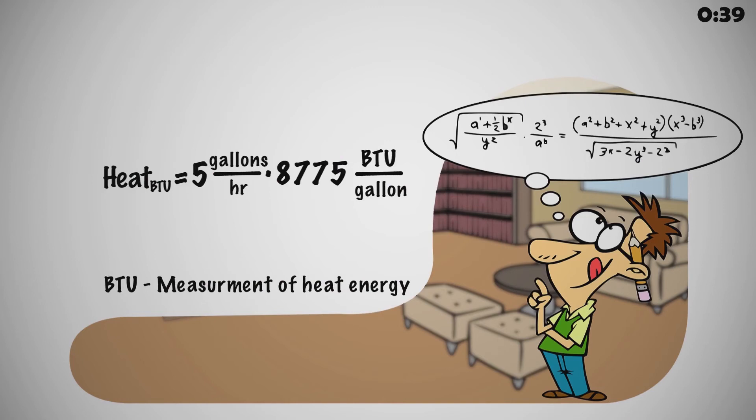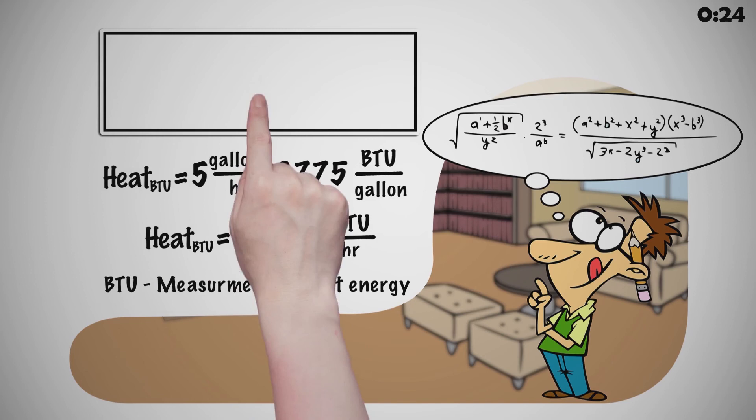Heat in the formula is expressed in BTU and equated to Power Breezer water evaporation at the rate of 5 gallons per hour multiplied by 8,775 BTU per gallon, totaling 43,875 BTU.